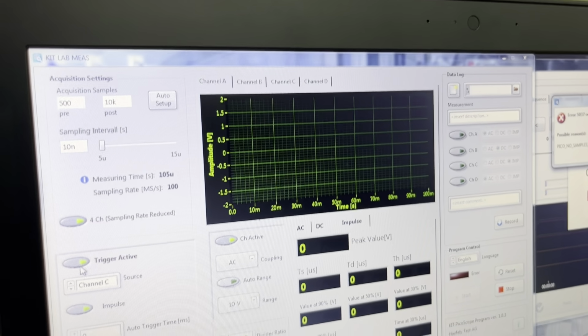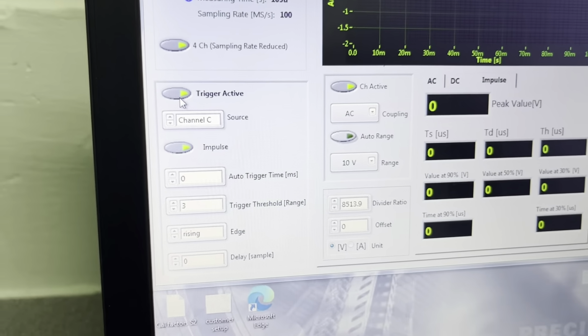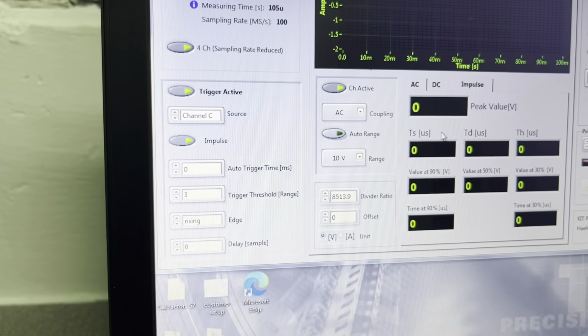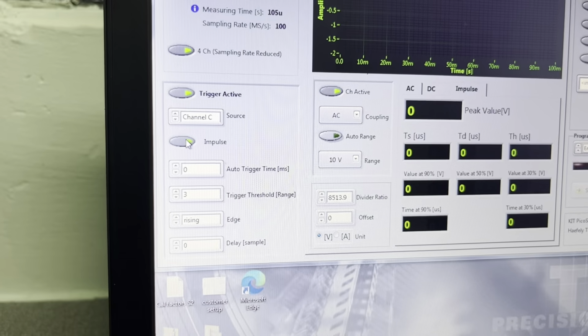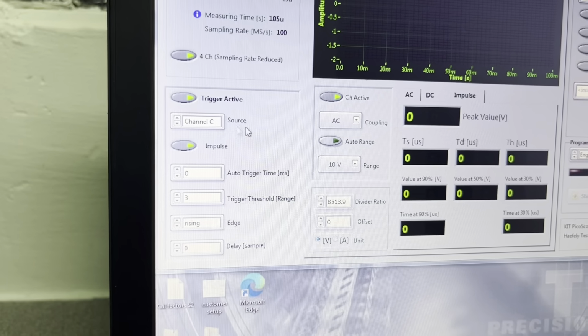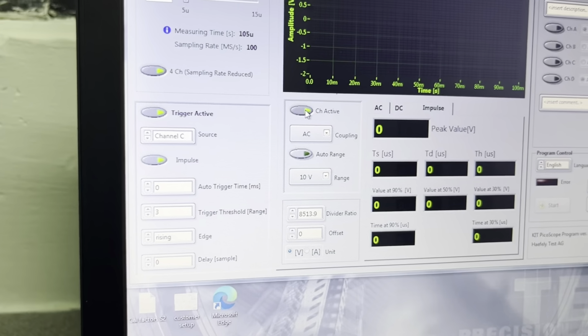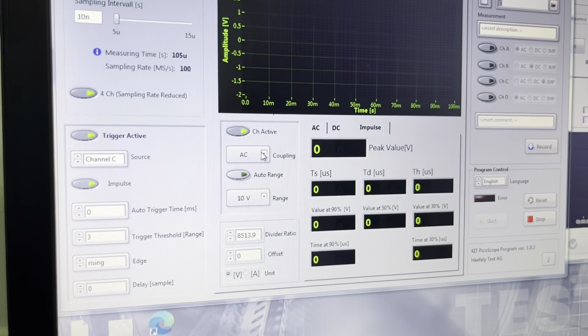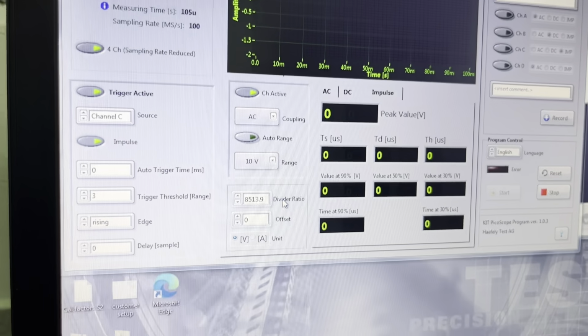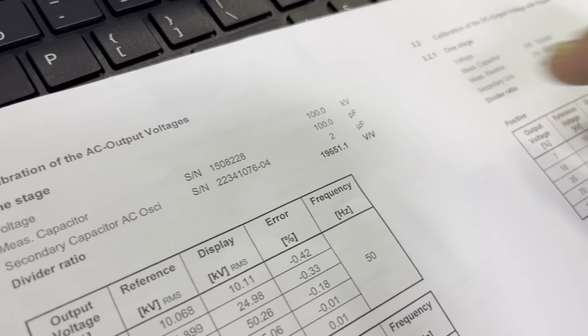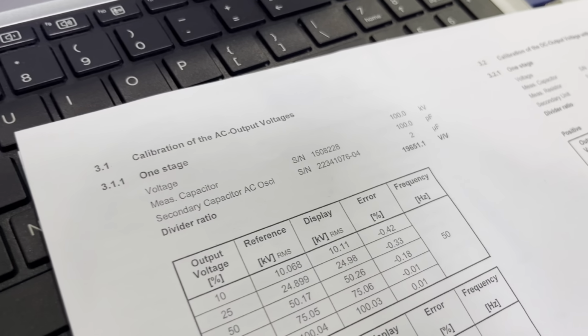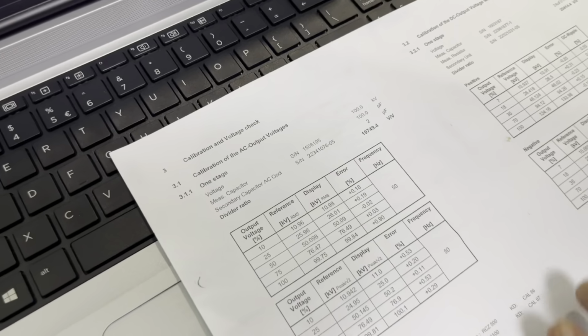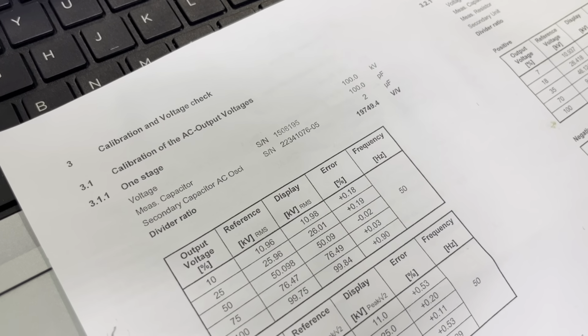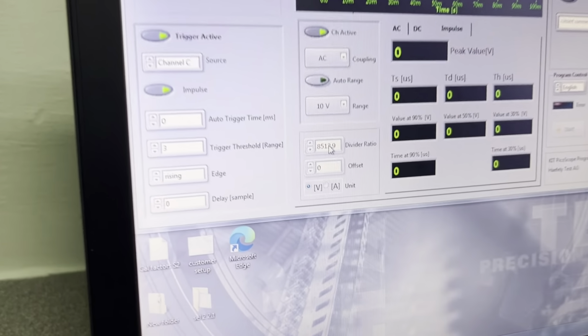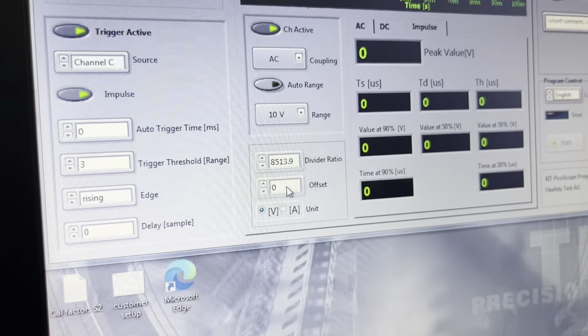Okay, next is we are going to set trigger. Trigger should be set to inactive. Impulse should be set to inactive since we are measuring AC HV. So channel, we are going to activate the channel, and coupling change it to DC. Okay, divider ratio. Once again, we will refer to our specification. We are going to input 19,641.1. Okay, sorry, that is a wrong specification. We are going to key in 19,749 at divider ratio. Offset we let it remain at 0.